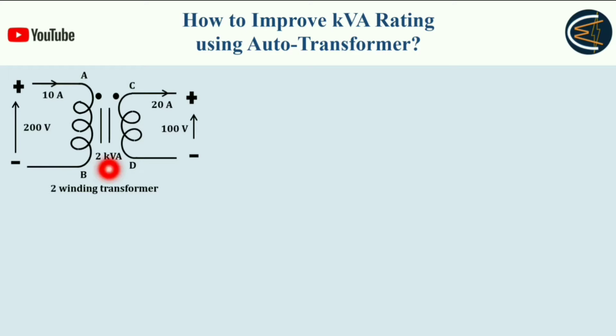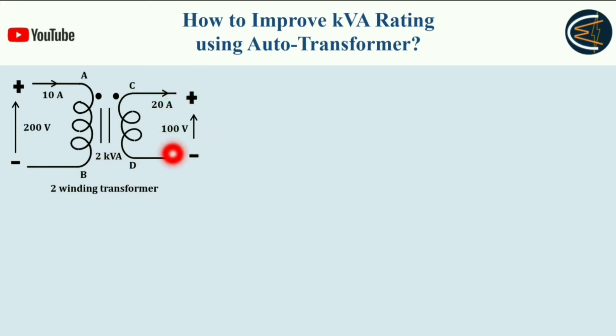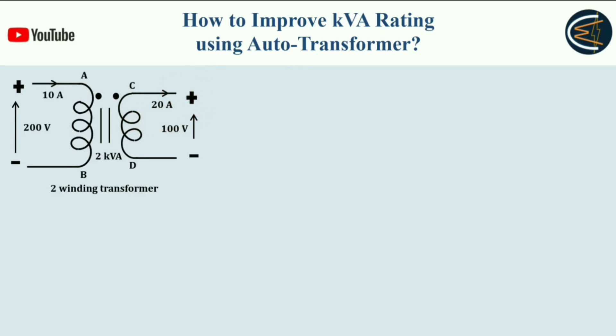So as you can see, this is a two-winding transformer — the normal transformer. The primary side is the high voltage side at 200 volts, and the secondary side is 100 volts. The rating is 2 KVA. For a rated load, the primary side current will be 10 amperes and the secondary side rated current will be 20 amperes.